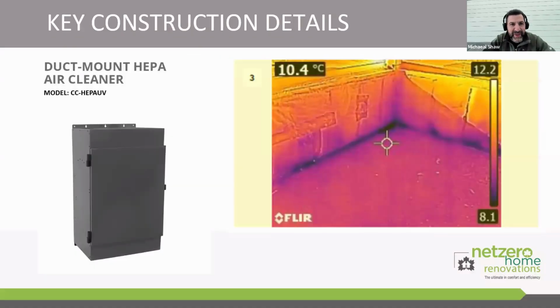What we're doing from an indoor air quality perspective is probably the stuff that's most exciting for us. We are putting in a duct mount HEPA air cleaner, and this HEPA air cleaner has a booster on it. So the static pressure drop you might experience with a normal HEPA filter - we can boost the pressure up so we don't see that static pressure drop. This HEPA air cleaner has HEPA and UV built into it, as I understand, and that'll get attached to our main mechanical system. We'll also have UV coils to prevent bacteria growth on the cooling and heating coils on the air handlers. So that's kind of the main way we're filtering air.